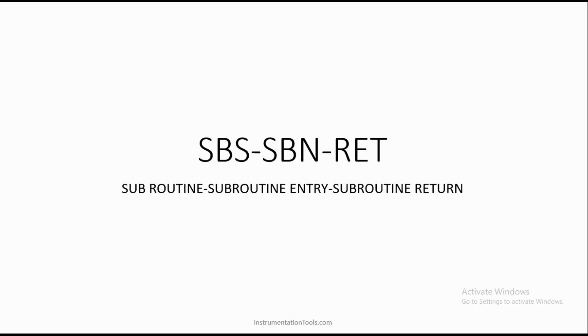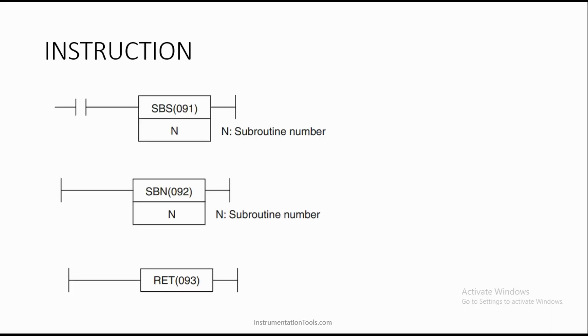We have three instructions: subroutine call (SBS), subroutine entry (SBN), and subroutine return. All three instructions must be used together. To use the subroutine concept, you need all three in your ladder logic. You identify which subroutine you are referring to by using the subroutine number — you assign a number to each subroutine and call it by that number.